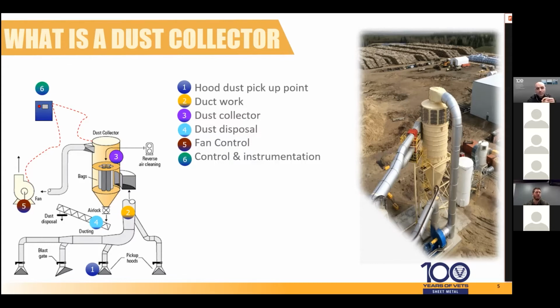And when we do our design in dust collection, we always account for containment, which is super important. Imagine a saw that's cutting a board. That saw will be spinning quite fast and will generate a lot of dust, and that dust will be projected at a high velocity everywhere. If you don't have a proper hood to capture that dust, you might get only 10-15% of all the dust generated. That's why different means are often put on saws to contain the dust, and then you can suck from the saw blade, and your rate of success in capturing the dust is quite a bit higher. So the hood design is really, really critical to be successful, as well as the containment.